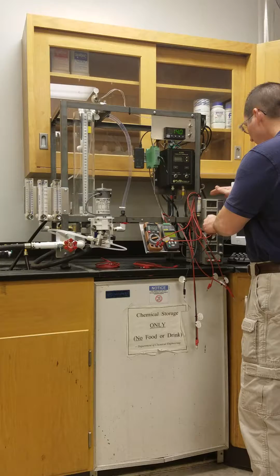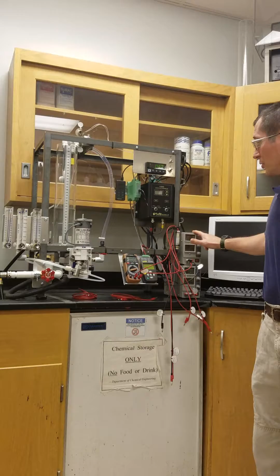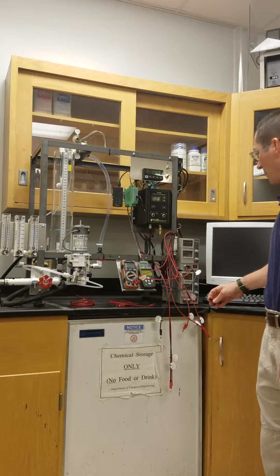The signal coming back goes back into the power supply there, so it makes a complete loop. That's something about 4 to 20 milliamp. It forms this loop. You have to have some kind of power to run the loop, and it has to flow all the way through the system and then back to the power source.